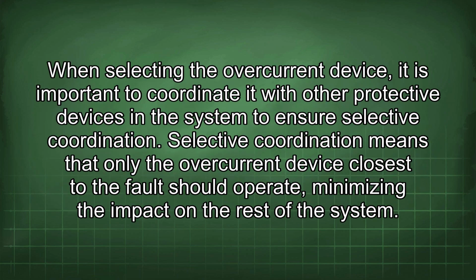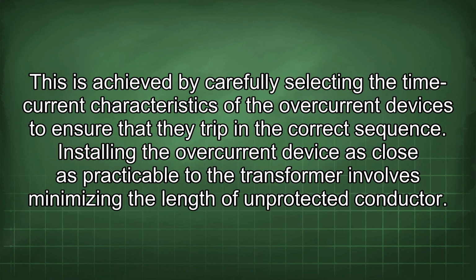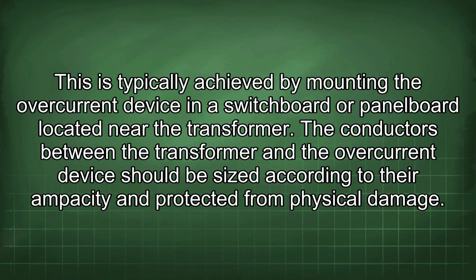When selecting the overcurrent device, it is important to coordinate it with other protective devices in the system to ensure selective coordination. Selective coordination means that only the overcurrent device closest to the fault should operate, minimizing the impact on the rest of the system. This is achieved by carefully selecting the time-current characteristics of the overcurrent devices to ensure that they trip in the correct sequence. Installing the overcurrent device as close as practicable to the transformer involves minimizing the length of unprotected conductor. This is typically achieved by mounting the overcurrent device in a switchboard or panelboard located near the transformer. The conductors between the transformer and the overcurrent device should be sized according to their ampacity and protected from physical damage.